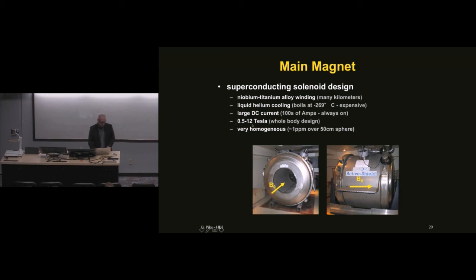To date, the range of magnetic fields used in imaging are maybe less than 0.05, but maybe 0.1, all the way up to the highest, I think 12 Tesla, that's ever been built that could put a human in. They also have to be very uniform, typically a uniformity over the size of the head of about 1 part per million. Those are the contributing factors that make them expensive.